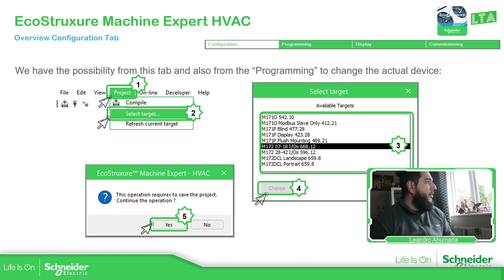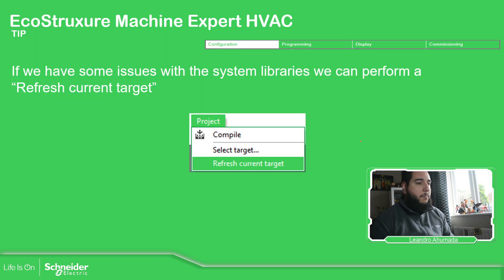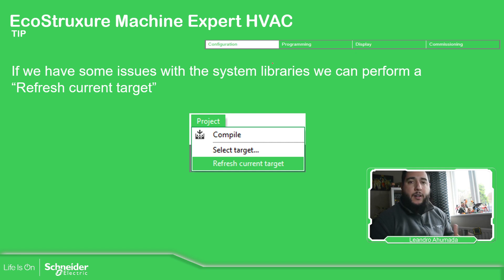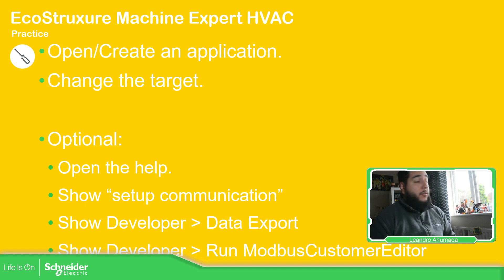To change the target, we just go to Project, select target, and then a window will appear showing all the available PLCs. We select the one we want and confirm the change. After the selection, it will ask you to save the project. One common issue I've found is that sometimes internal libraries are not recognized by the application. In those cases, I recommend going to Project and selecting refresh current target — it's like a clean build, and that resolves the problem.